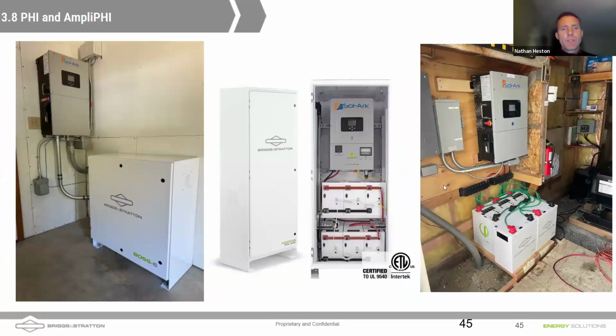Here are some examples of systems. This is using the Boss 6 cabinet. So it's got 25 kilowatt hours of storage inside it. You have the ability to put heaters in with this example as well. This is a nice looking system where they've chosen not to do a wire gutter underneath. And it looks like they've got an input or an output below. That might be a generator input below the inverter there. Here's an example of an access cabinet. We showed that earlier.